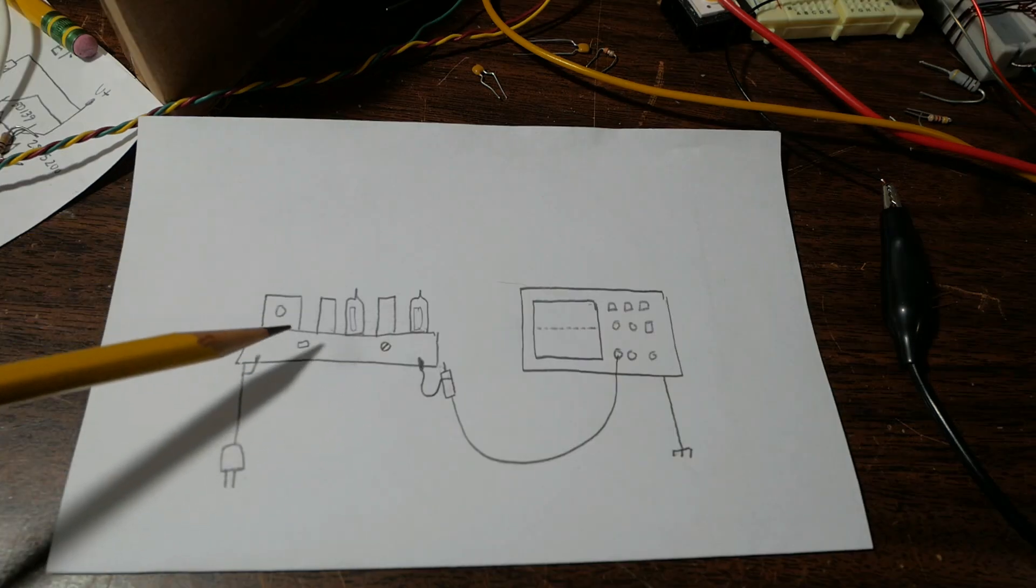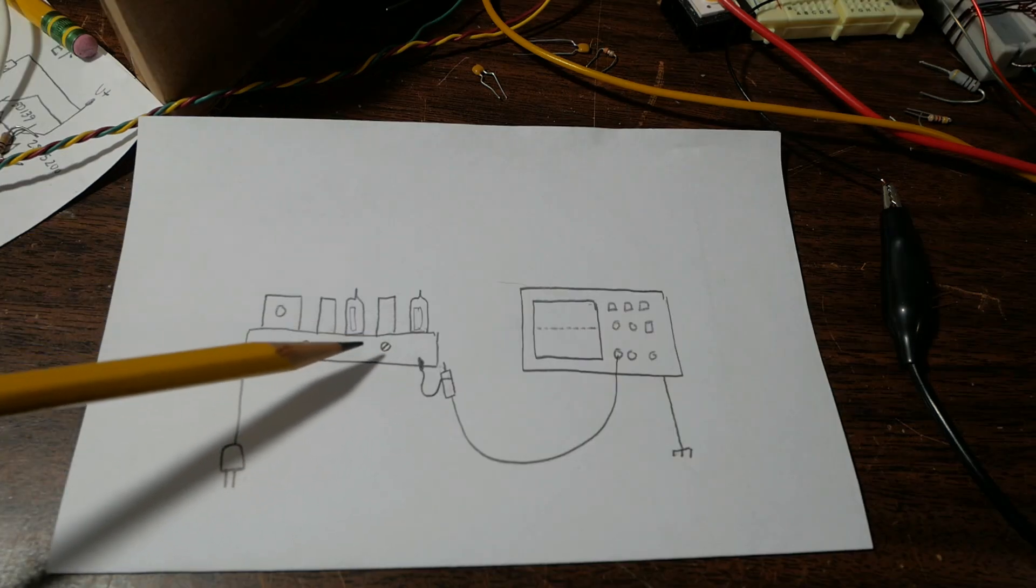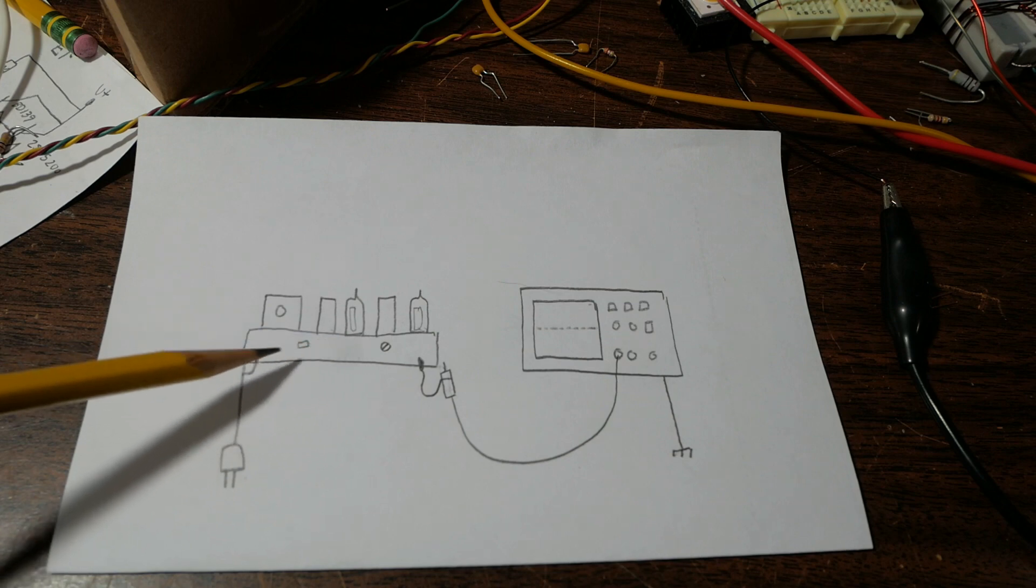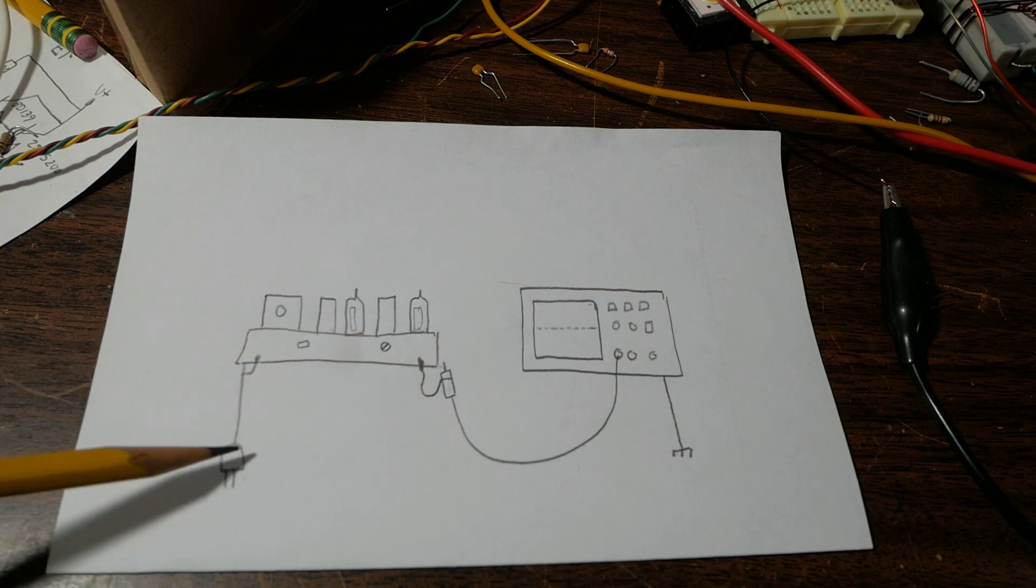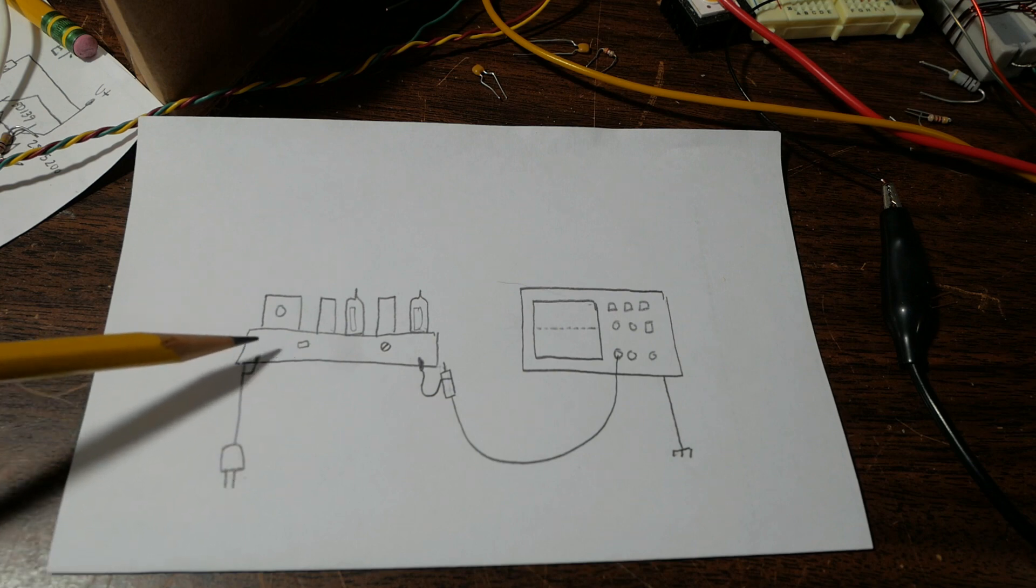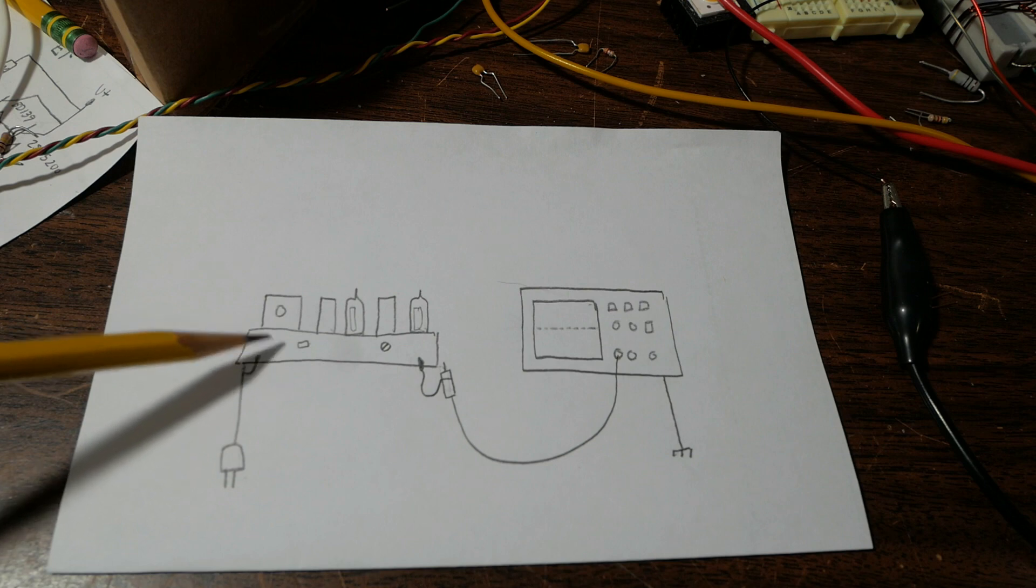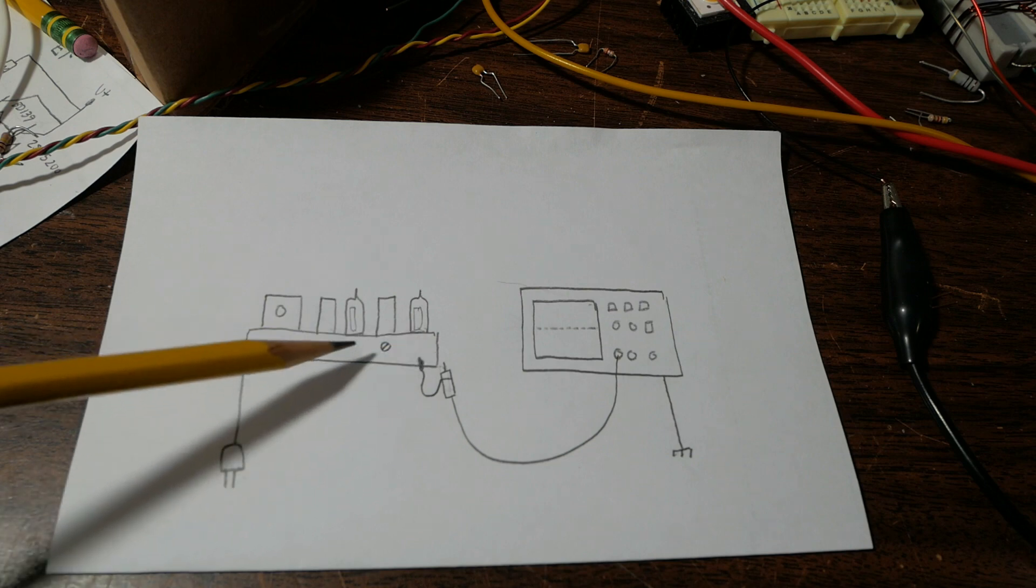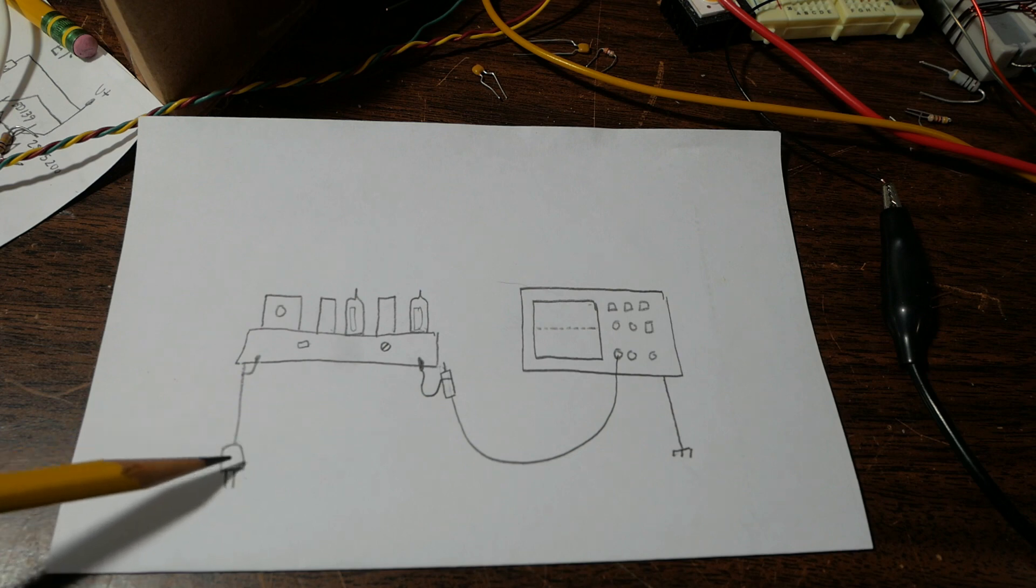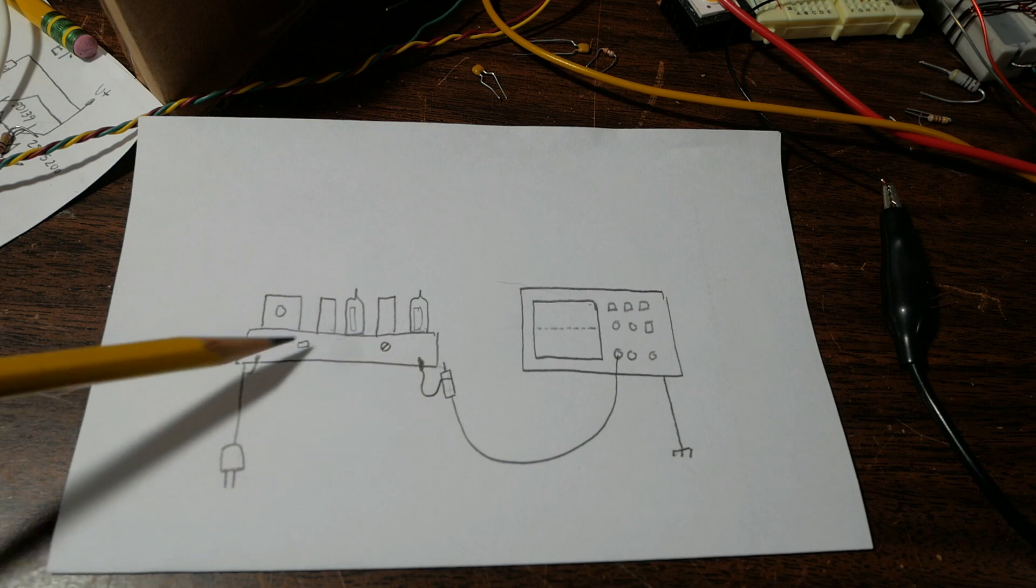Another scenario that is hazardous and potentially deadly is the hot chassis or live chassis type situation, where one side of the electrical supply or mains is connected to the ground or actual metal part of the chassis.